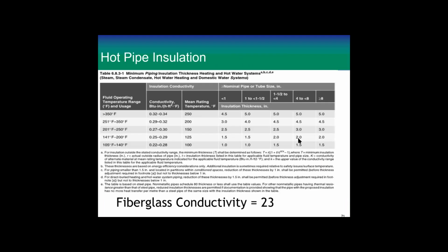and they are minimum requirements. Here's the one for piping. This is for hot pipe insulation. So this is the conductivity of the insulation. This is the mean rating for that insulation, so you'll know how hot it is. And this is the fluid temperature that it applies to as far as our code. So notice that we don't require insulation on a hot pipe that's cooler than 105 degrees. And then we require, based on the pipe size, a certain insulation thickness. And this equation is important.